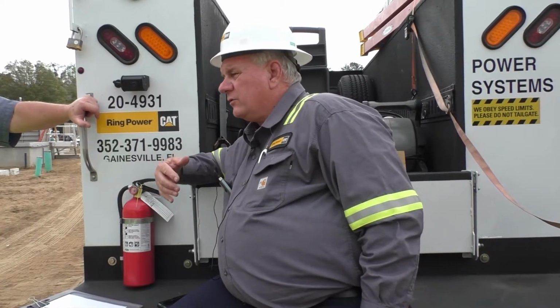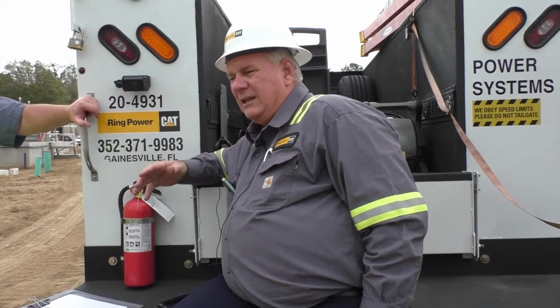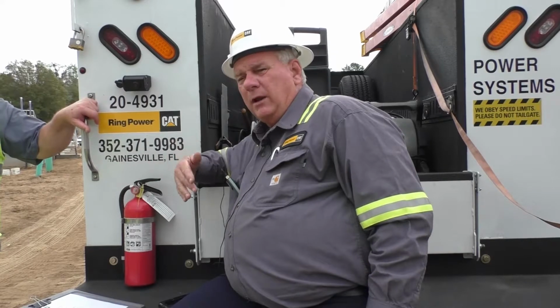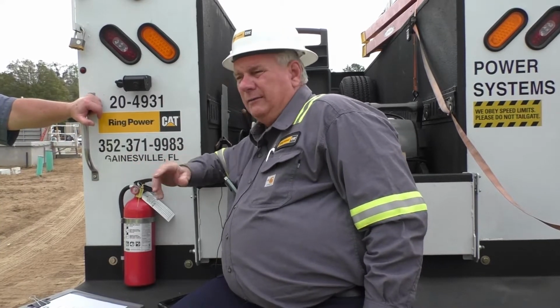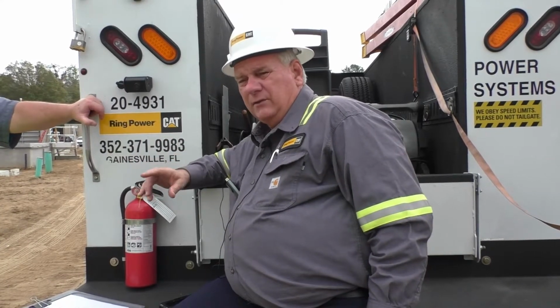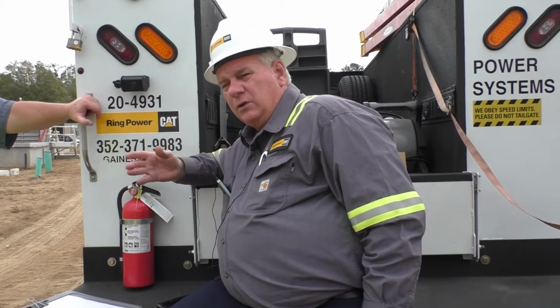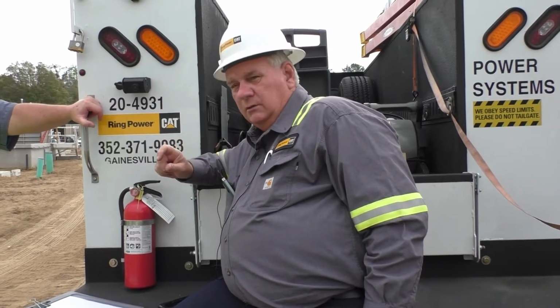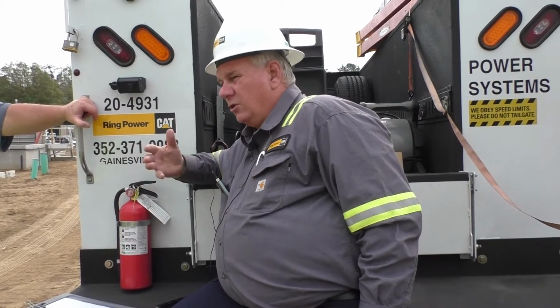All right. These transfer switches are called delayed transition, which means they open the breaker that they're on. They wait whatever the time delay is. It can be 2 to 5 seconds, and then they close the breaker they're going to. So the whole plant's going to go dead for that period between sources, and that's a normal condition.